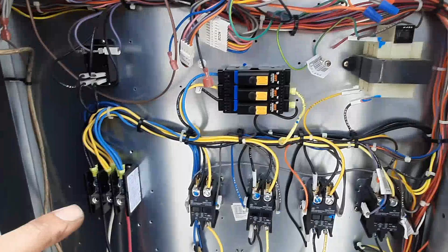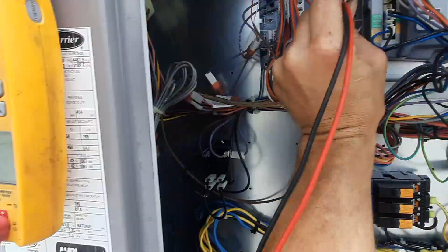So nothing too out of the ordinary, except my display on the Jade is blank. I don't know why this wire is just hanging there. Yeah, I got no voltage. And I verified 3-phase at my disconnect, but we can verify here. So I got 3-phase. Let's see here. I'm not tripped there. Smoke detector maybe. That would have my power cut off.